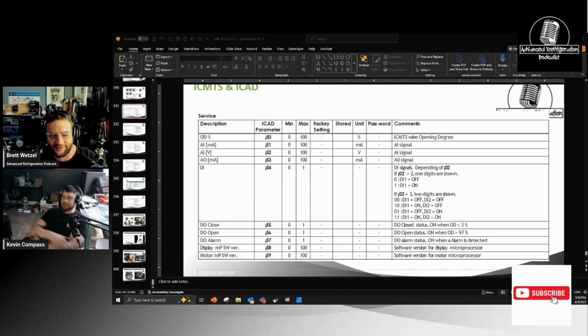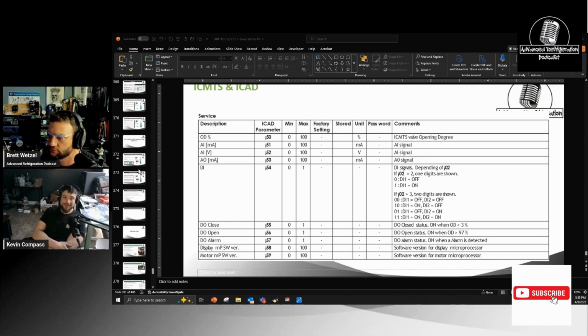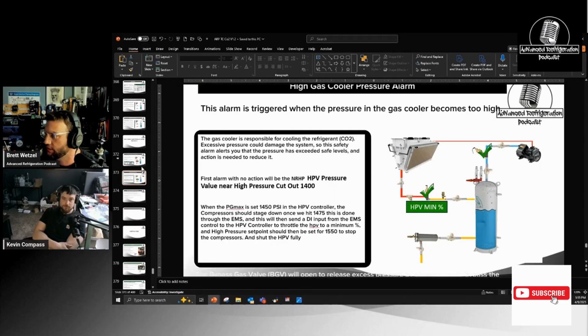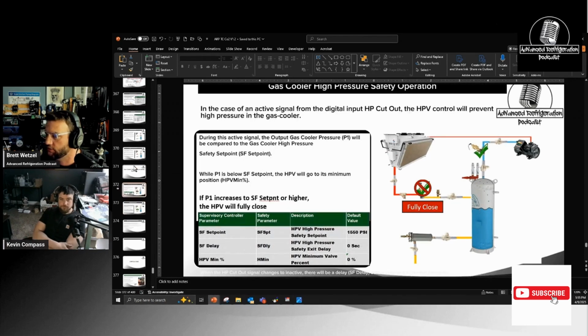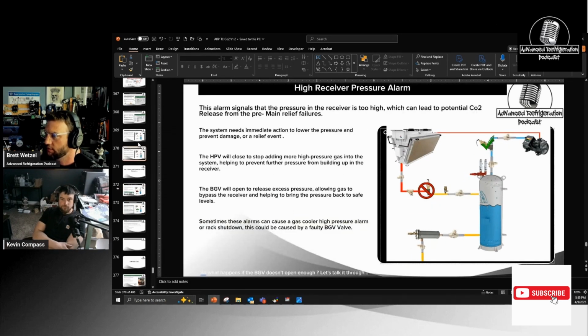Okay, continue. Yeah, if you had stainless piping, you're going to be doing that a lot. And then, other than that, after you keep them clean and if they're wired right, you shouldn't have any issues besides here and there. And if your head pressure is too low and you're having issues with that, most of the time gas cooler control kills more valves than anything. Gas cooler high. Gas cooler high. So I guess I don't have that.